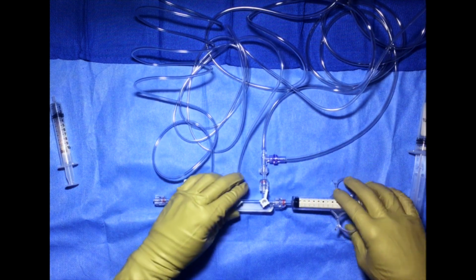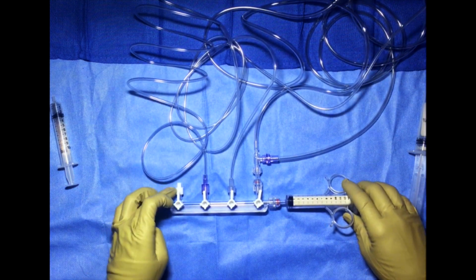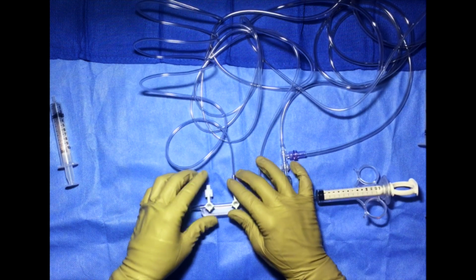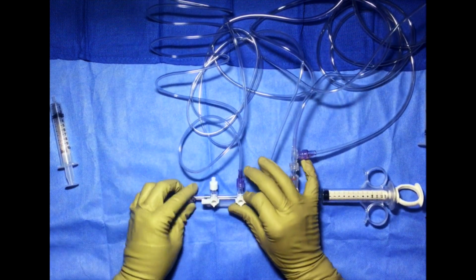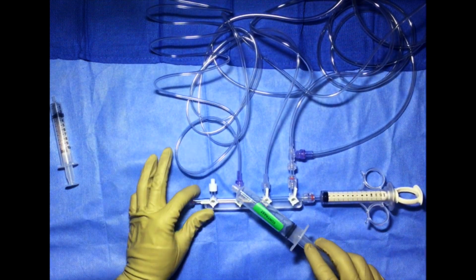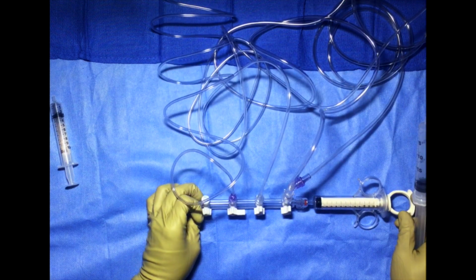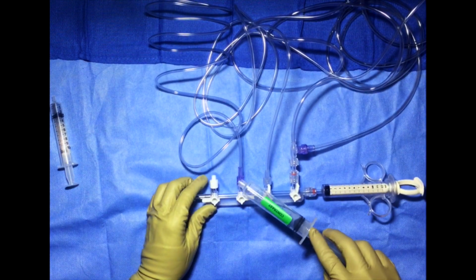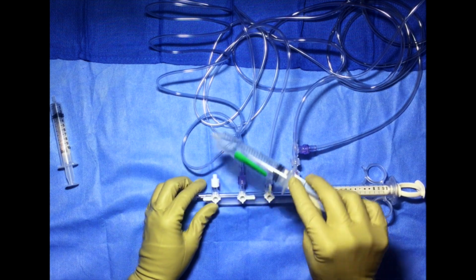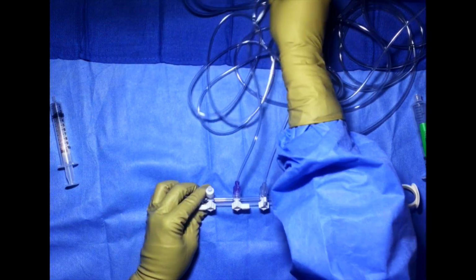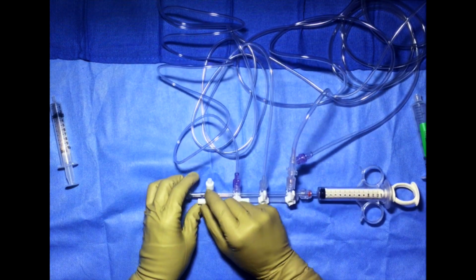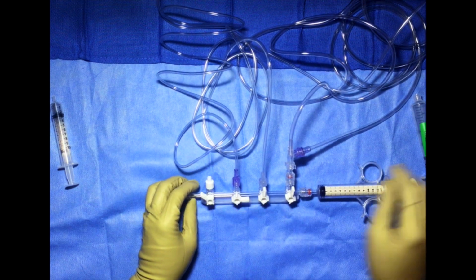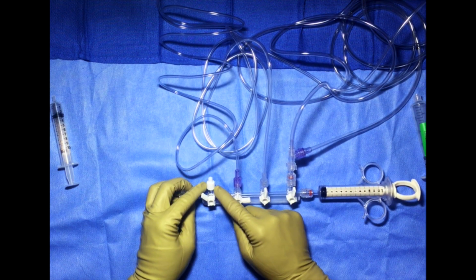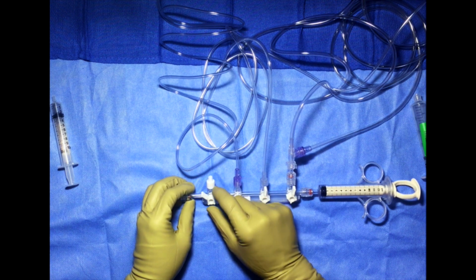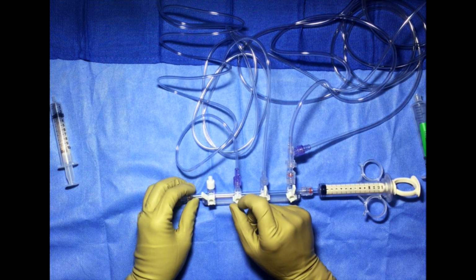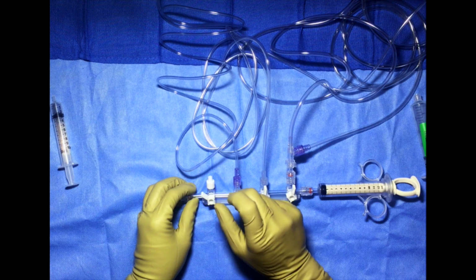Now, if that was all clear, and you did the transducer last, I'd come over here, I'm going to turn this on, I'm going to tap, tap, tap, and this is going to be up this way, but so you can see, I'm going to tap, tap, tap, fluid coming out this way, okay, and then when I get done, everything looks good, no bubbles. And you do have to be careful tapping on the transducer. You can break it. Even just the transducer is sensitive, so just the sensor you could bust.